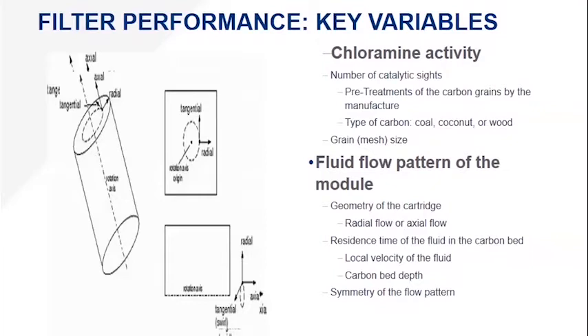There's always a balance in filtration between removal and pressure drop. Fluid flow pattern of the filter matters as well — the geometry of the cartridge, radial flow versus axial flow. Radial flow goes from the outside of the filter inward, and the bed of carbon is the full diameter of the filter plus the core. Axial flow goes down the length of the cartridge. Most of our cartridges are radial flow; our inline or GAC filters tend to be axial flow, and you'll tend to experience more pressure drop with axial flow cartridges.